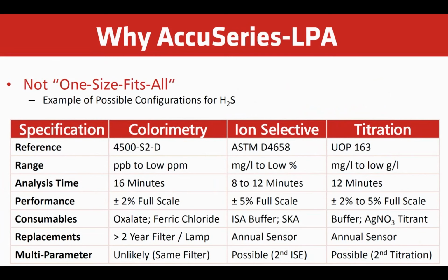Different replacements for colorimetric, obviously we want to replace the optical filters and lamps every 2 years, but ion selective electrode is annual ISE probe replacement, or titration yearly pH probe replacement. If it's multi-parameter, it's possible on an ISE in titration, but generally not possible on colorimetric, that it would actually use the same filter for the measurement.